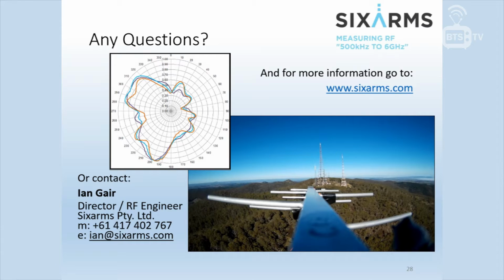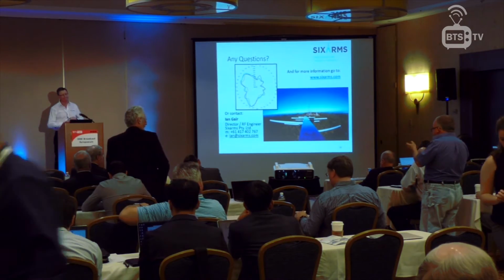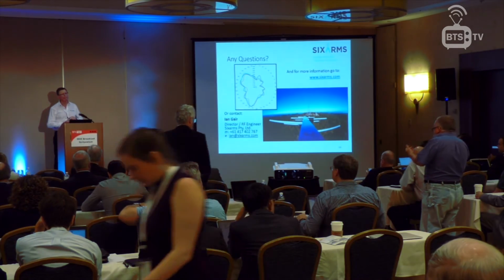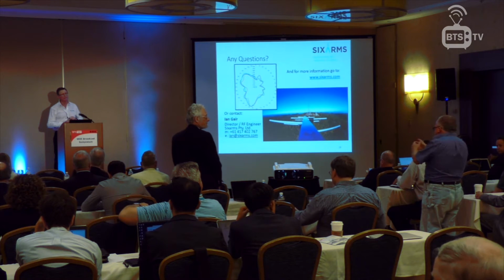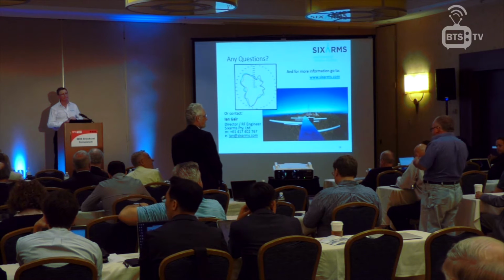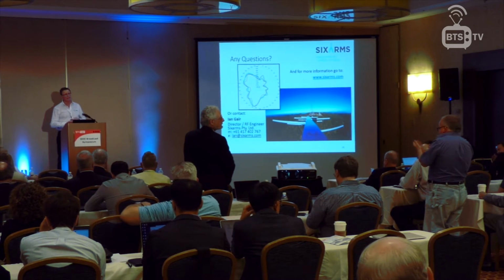When you're flying close in like that, I would assume you can still find problems, like you mentioned earlier, with inverted panels and other types of mounting issues. They would still show up, not as clearly as when you're further out and everything combines, but you can still find that null.